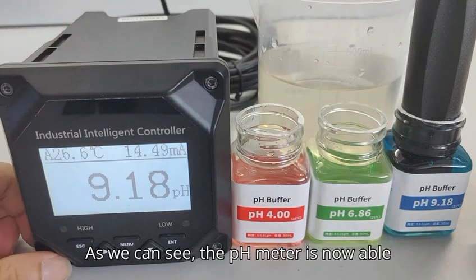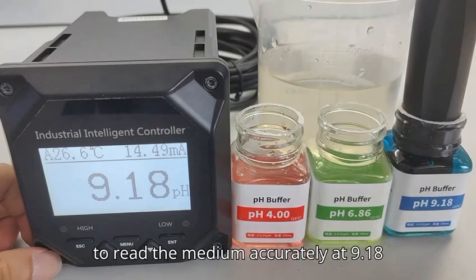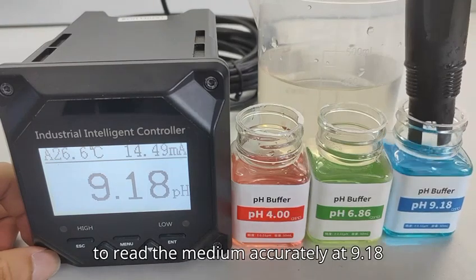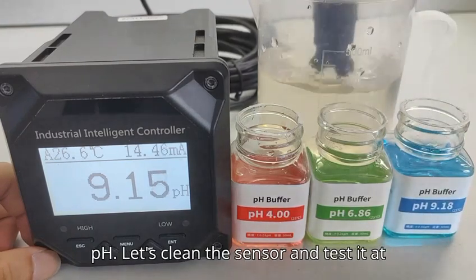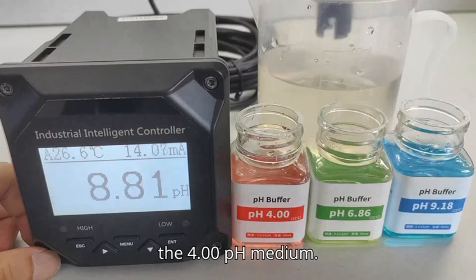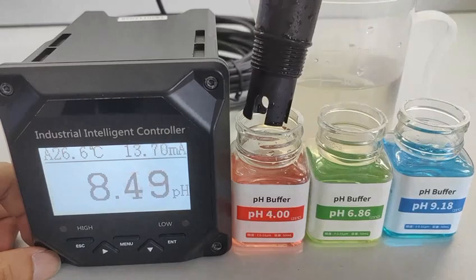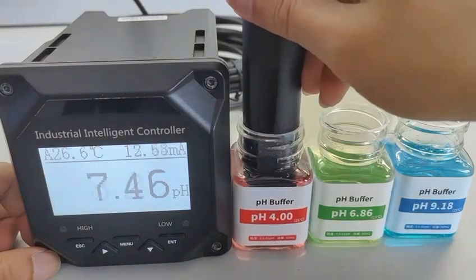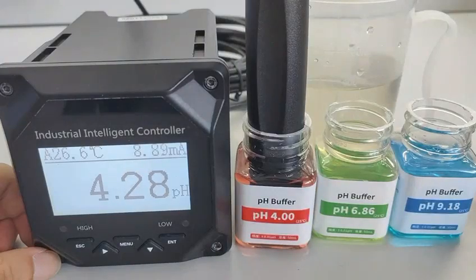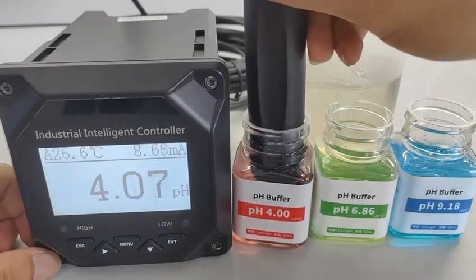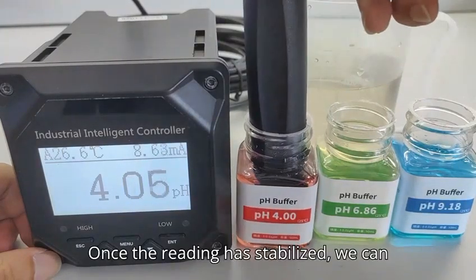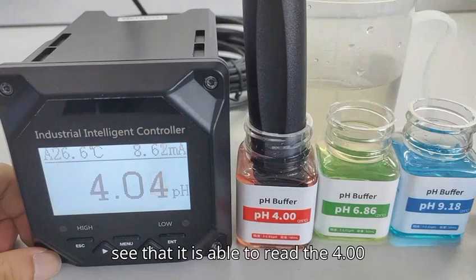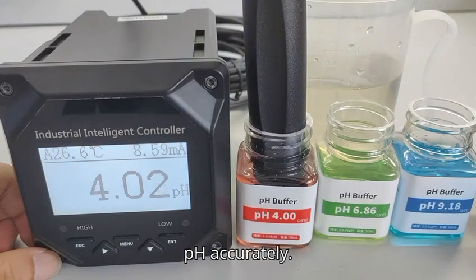As we can see, the pH meter is now able to read the medium accurately at 9.18 pH. Let's clean the sensor and test it at the 4.00 pH medium. Once the reading has stabilized, we can see that it is able to read the 4.00 pH accurately.